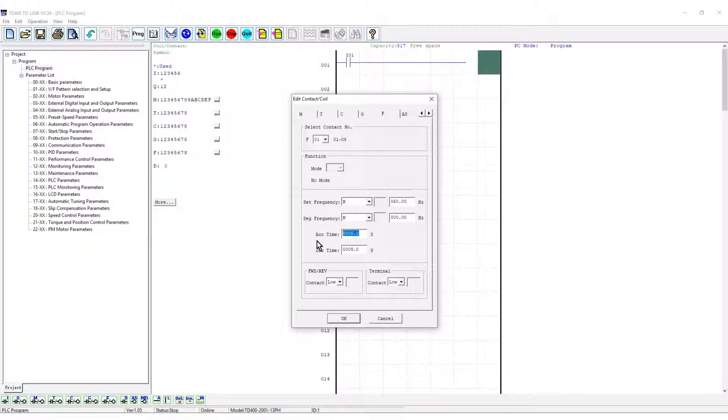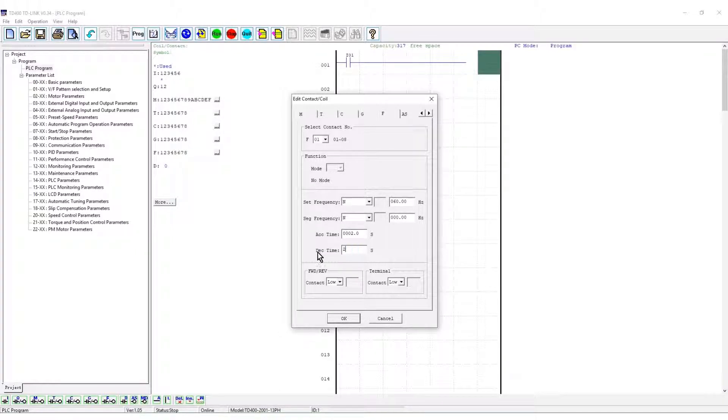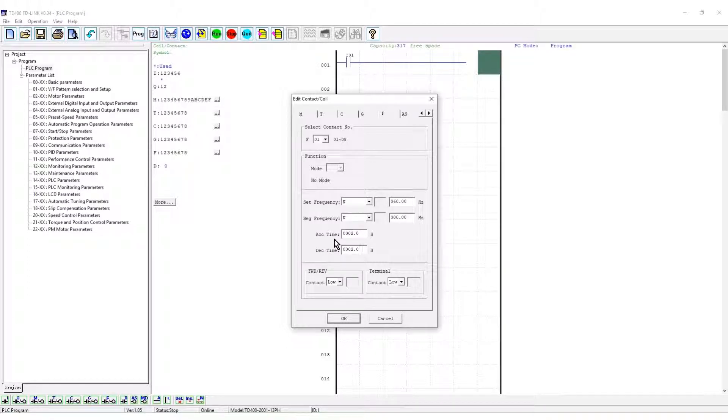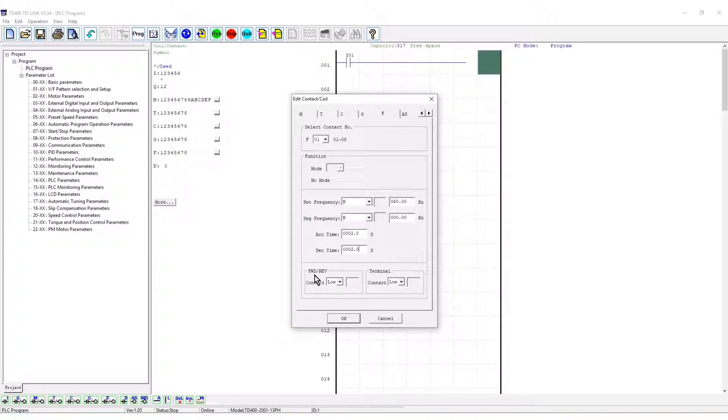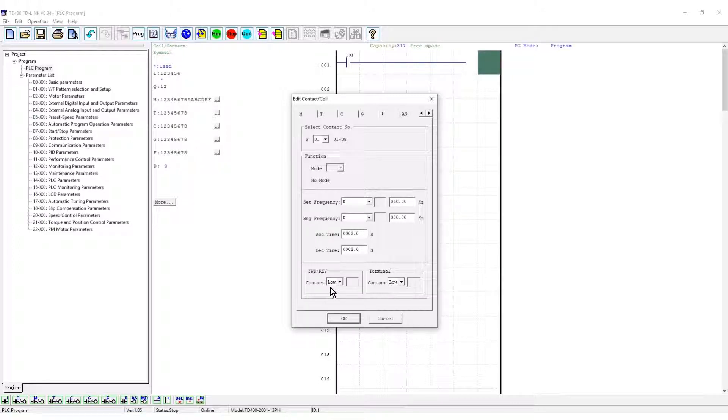The acceleration and deceleration times are set for 2 seconds. The directional control is left at low. This drives the motor in forward direction under PLC control. Click OK.